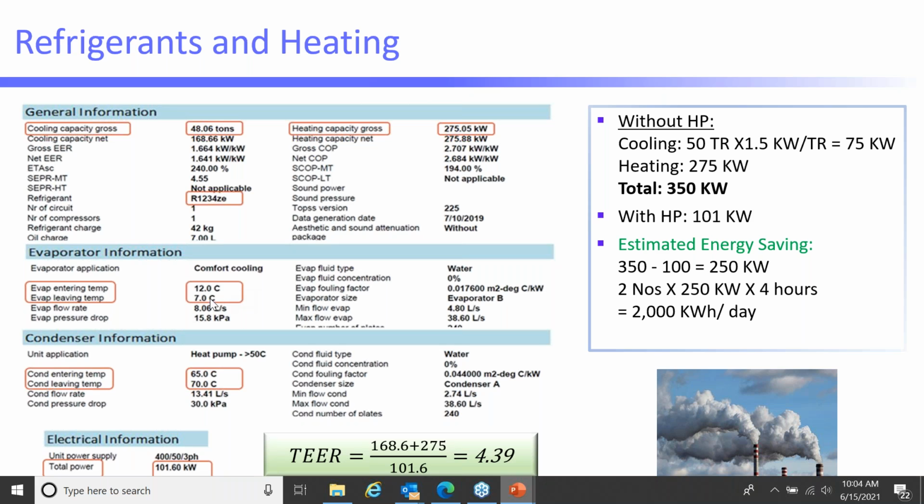And that heat pump is giving chilled water, let's say 7 or 12, so it's providing cooling. And at the same time, it's providing hot water at 65 to 70 degrees. So now we can really use water source heat pumps using refrigerant R1234ZE to meet the requirements of the heating demand of the domestic hot water.